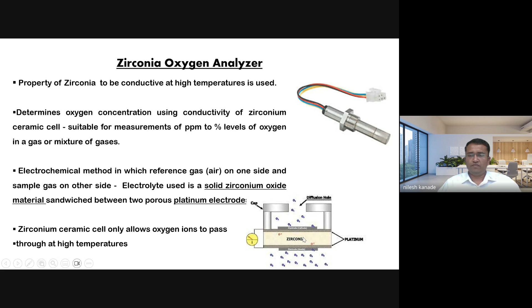The zirconia sensors work with conductivity measurements. When the zirconium oxide layers are heated up to 750 degrees centigrade, ionization starts. When any gas passes over these zirconium oxide layers, it carries ions along with it, and the ions move from one pole to another. It creates a potential difference, a millivolt signal. That millivolt signal is processed with the help of instrumentation and an amplifier, and it is usable for the measurement of oxygen gas. It is directly proportional to the oxygen gas concentration.